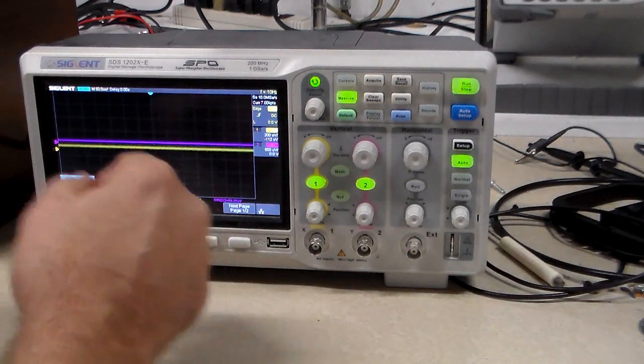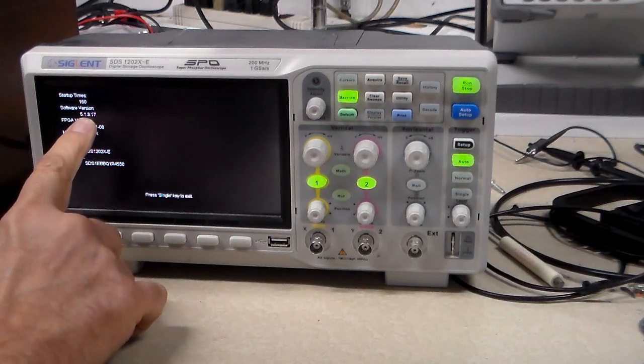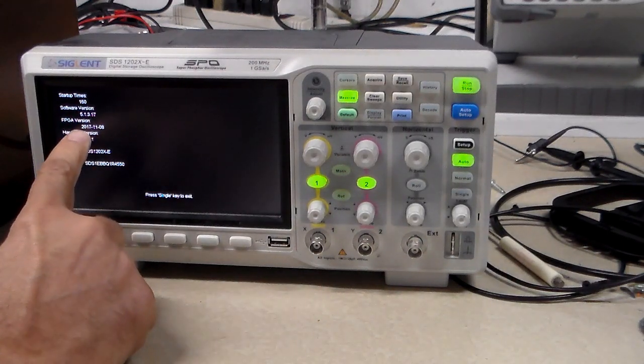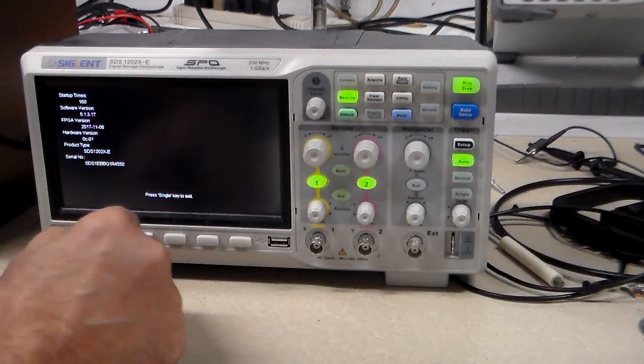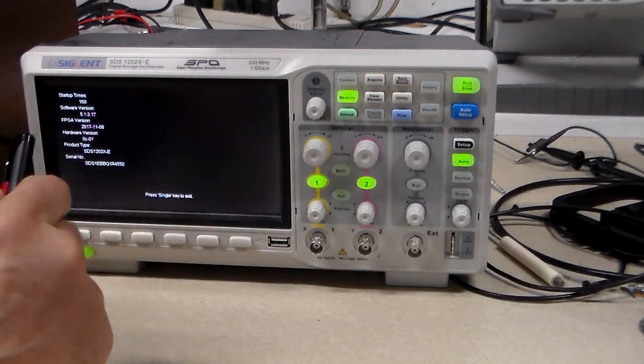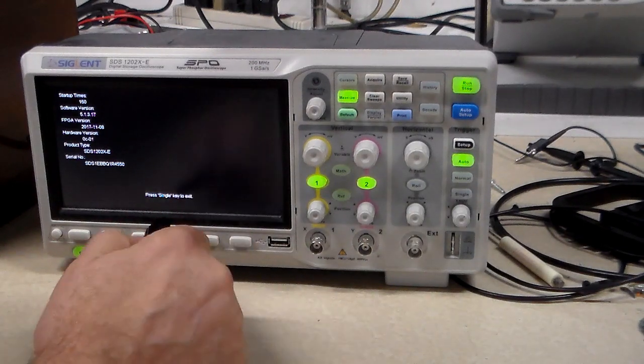I was looking on there and I wanted to see what software I had. I went to Utility, then System Status, and it tells me software version 5.1.3.17. The date on it was from 2017. I looked and there's a new version available, so I'm going to download it. I've already downloaded it from the Siglent North America website onto this thumb drive and we'll give it a shot.